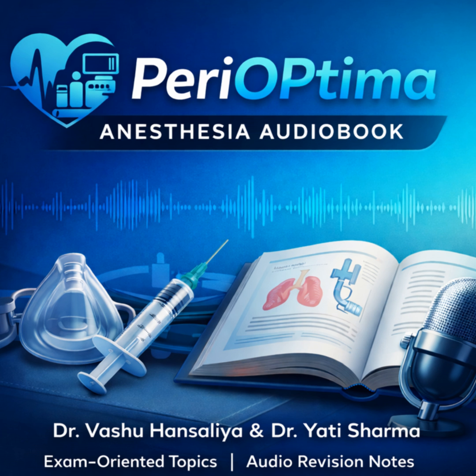All right, let's move downstream to the pressure regulators. We mentioned they drop the pressure, but there is a nuance about why they drop it to specifically around 45 psi. This is a beautiful piece of passive safety engineering. The hospital pipeline supply, the gas coming from the wall, usually runs at about 50 to 55 psi. The regulators on the machine are deliberately set to reduce cylinder pressure to a slightly lower level, around 45 psi. Why the intentional difference? What does that do? It creates a pressure gradient.